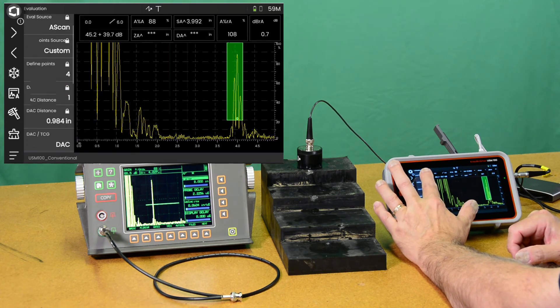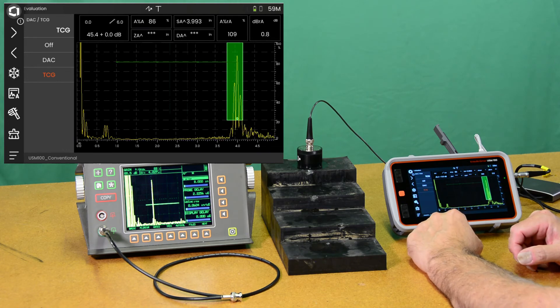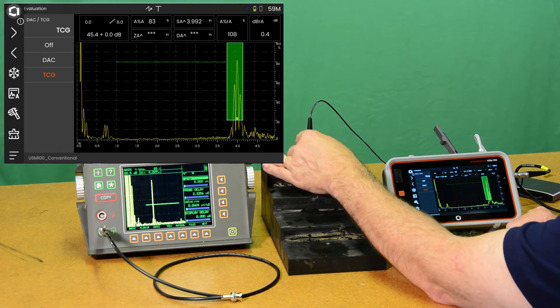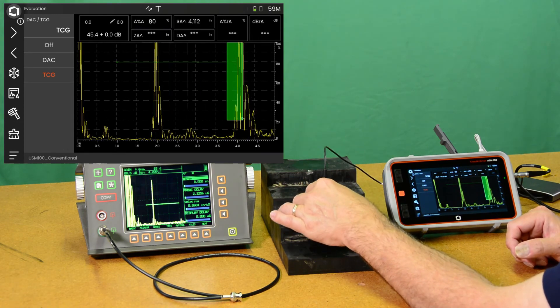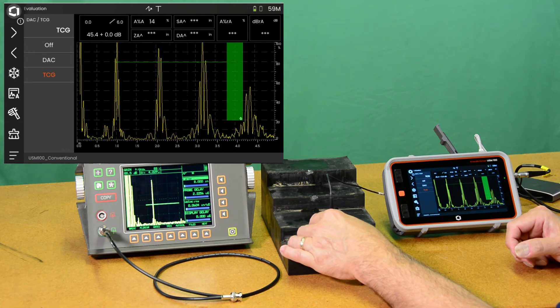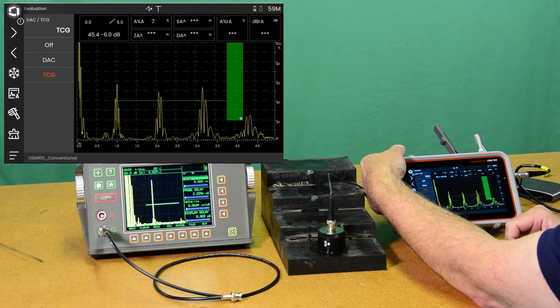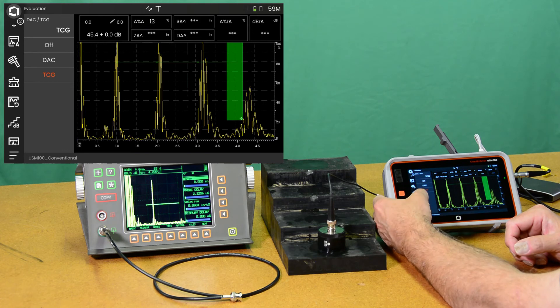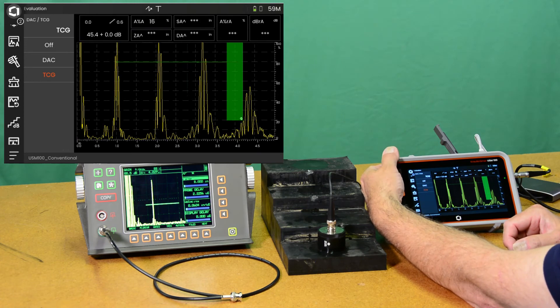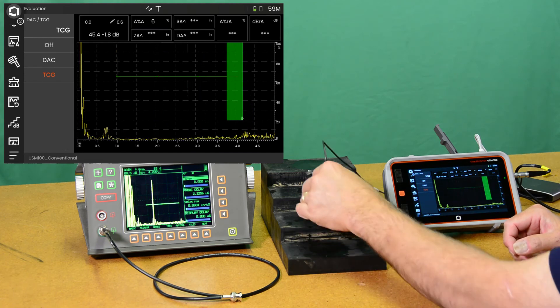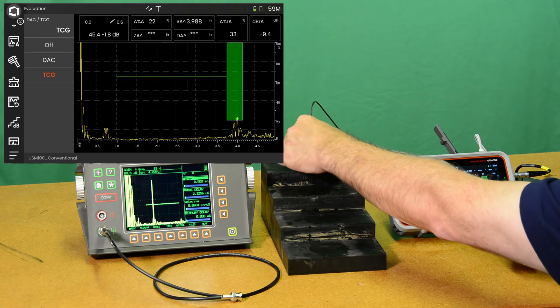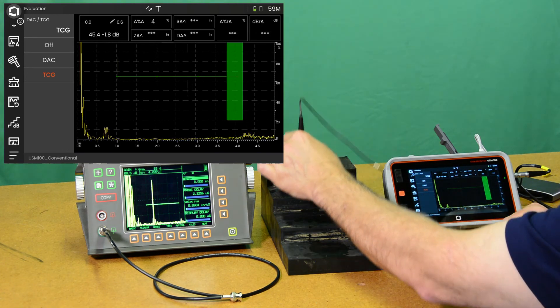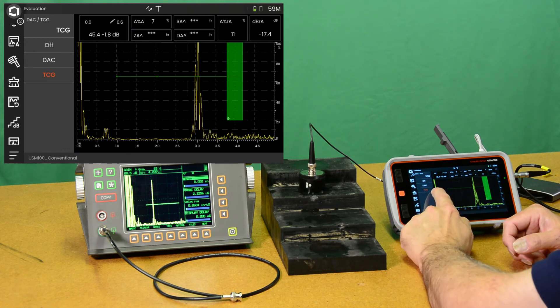And if I scroll down in this menu a little bit and I switch from DAC mode to TCG. Now I have a gain curve set up for TCG, which allows me to get a nice echo on any of the four steps. It's a little hot there. So I can take a couple of dB out. I need to choose a little finer gain steps now. So let's go back to half a dB. Take half a dB out. So that gives me pretty usable steps.